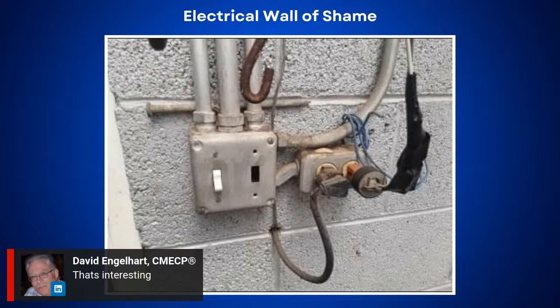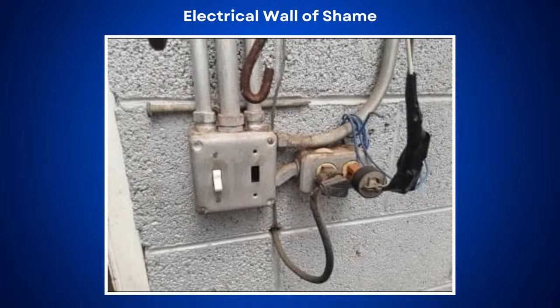Yeah, and I will do some more research, David, but I'm pretty sure that those offset nipples are not listed for use with a lock ring. We run into this all the time, just so everyone knows. If you have an EMT connector and you're going into a bell box, those threads aren't matching. A bell box is only listed for RMC. So yeah, you could take that offset nipple right into a bell box and then go to RMC. That's basically what it's designed for.